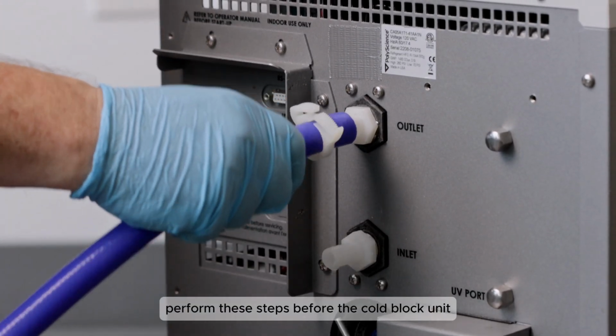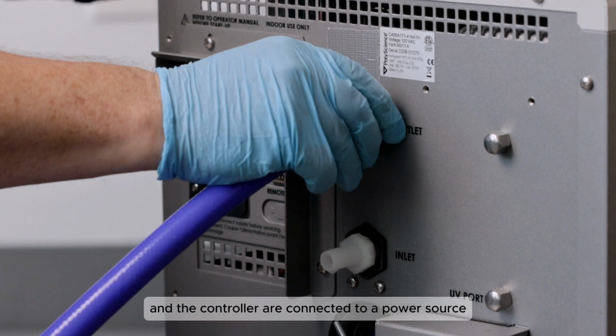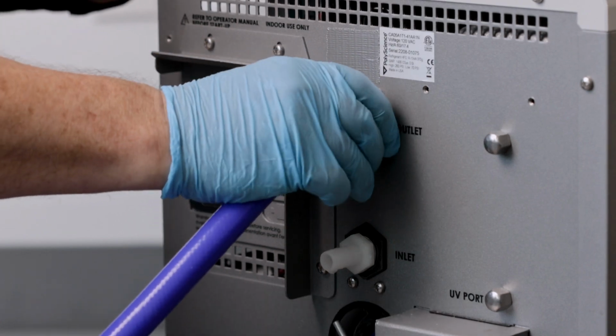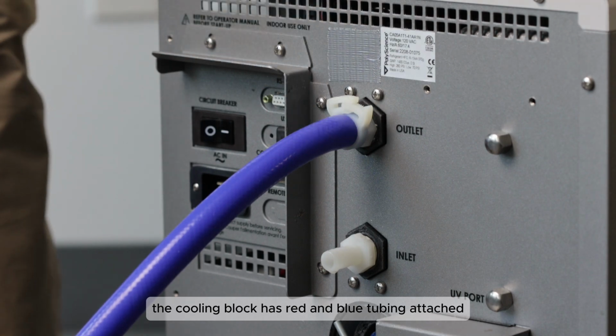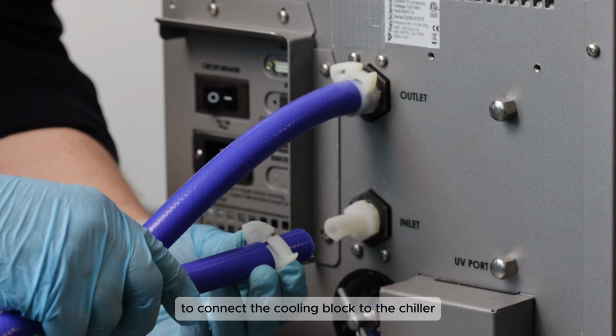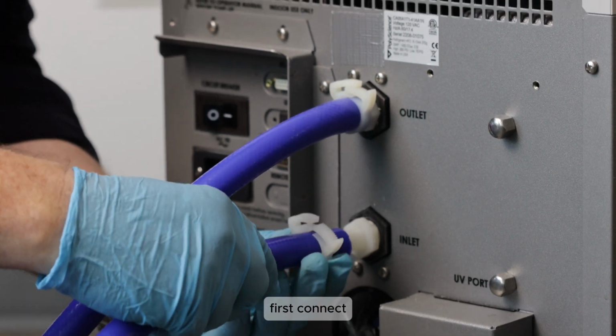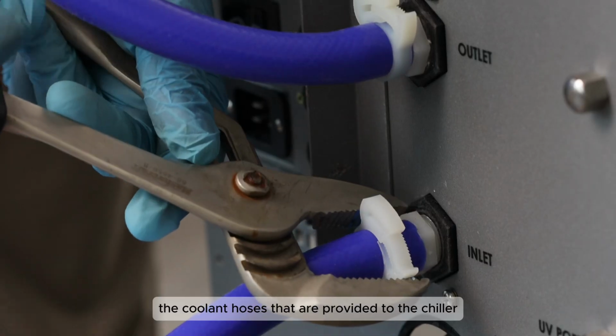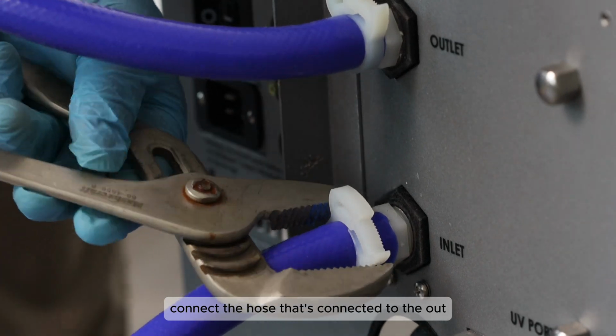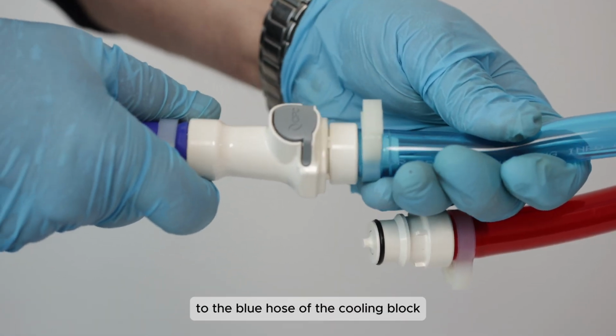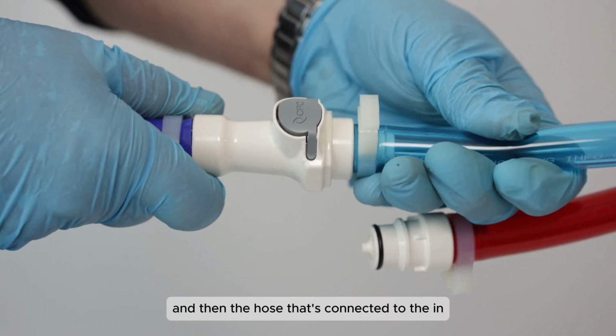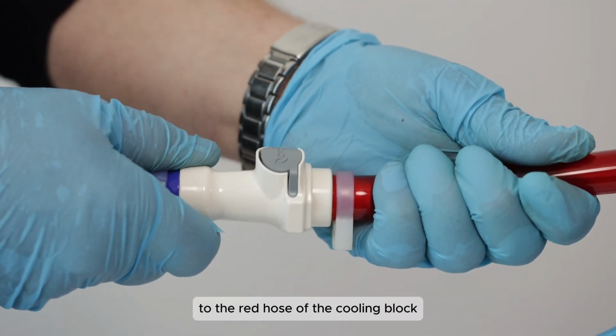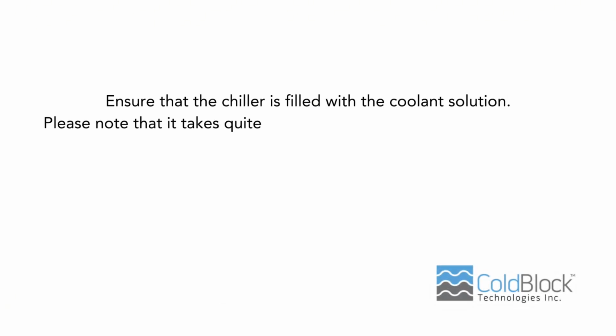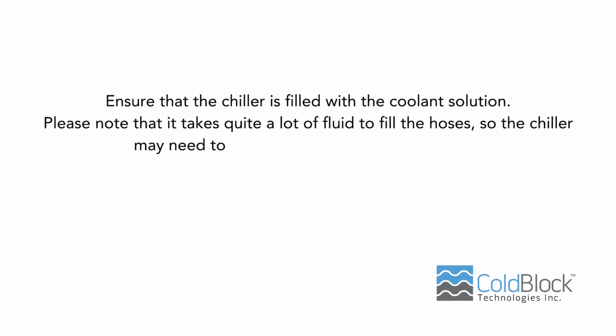Connect the unit. Perform these steps before the ColdBlock unit, the chiller, and the controller are connected to a power source. The cooling block has red and blue tubing attached with a quick connect fitting. To connect the cooling block to the chiller, first connect the coolant hoses that are provided to the chiller. Connect the hose that's connected to the out outlet port of the chiller to the blue hose of the cooling block, and then the hose that's connected to the inlet port of the chiller to the red hose of the cooling block. Ensure that the chiller's filled with the coolant solution. Please note that it takes quite a lot of fluid to fill the hoses, so the chiller may need to be topped up once it's operating.